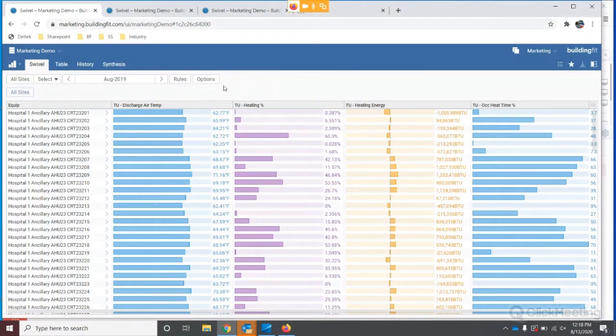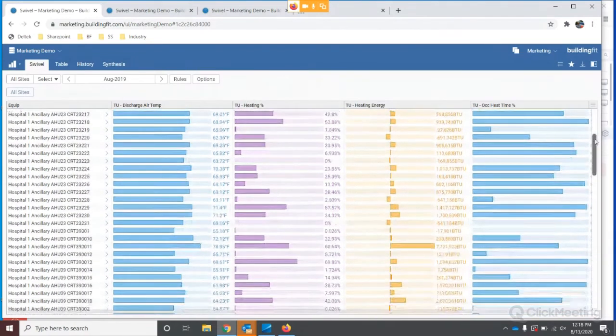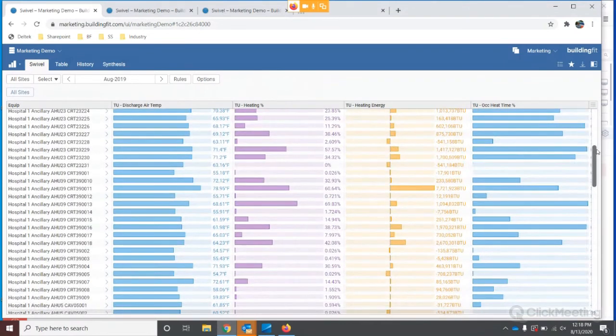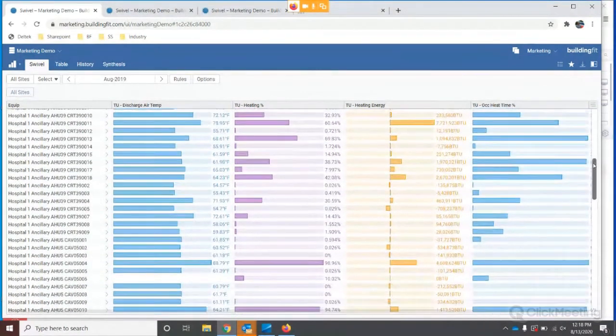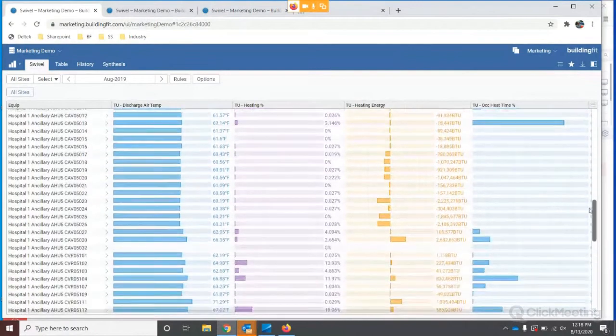For example, with heating energy, there are a number of types of heating systems involved. Say a hot water valve position is one of them. We're looking at the percentage open over a period of time for hot water valves as they're included in this heating percentage number. If we've got a couple hundred terminal units in an office building or a hospital, we can sort all of these.